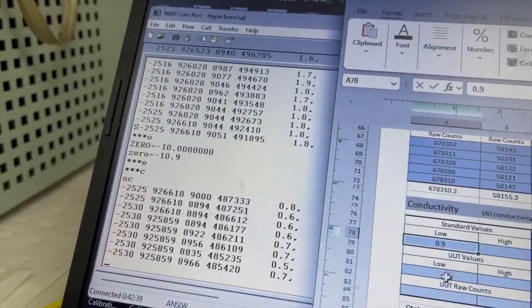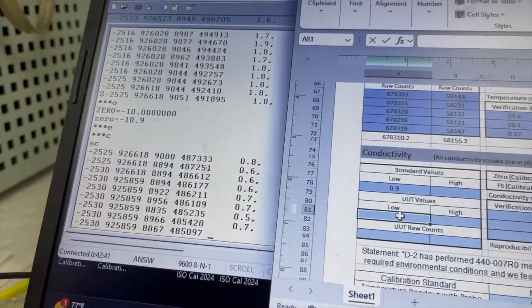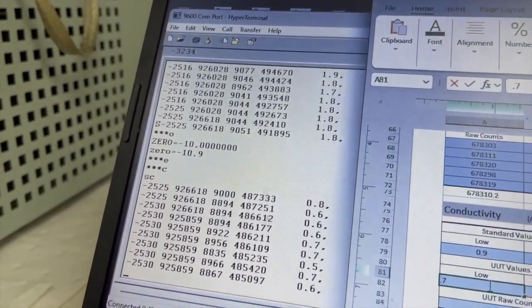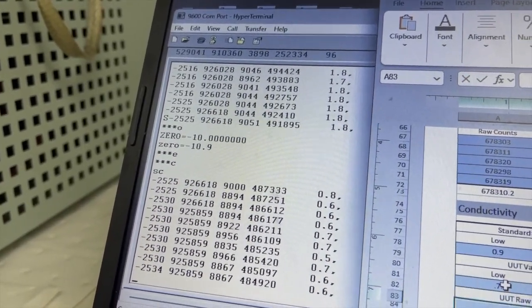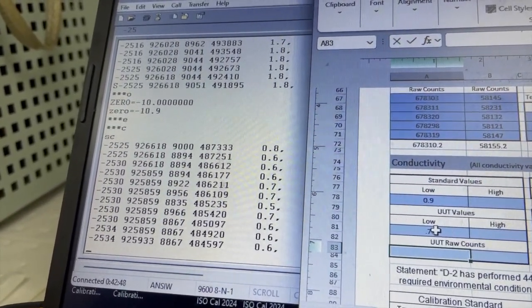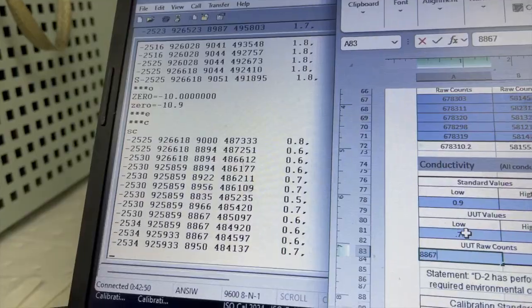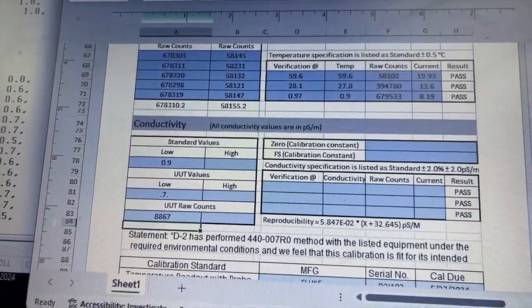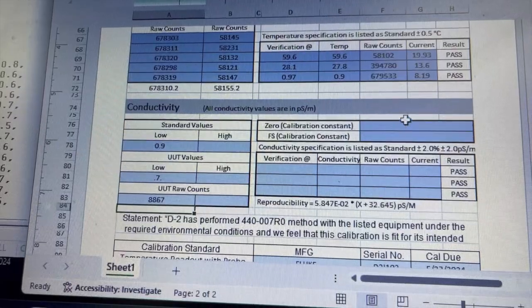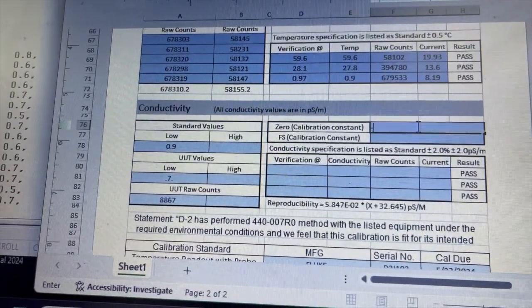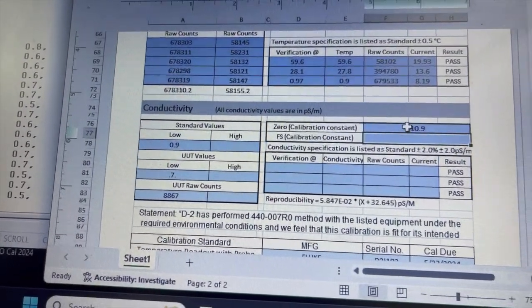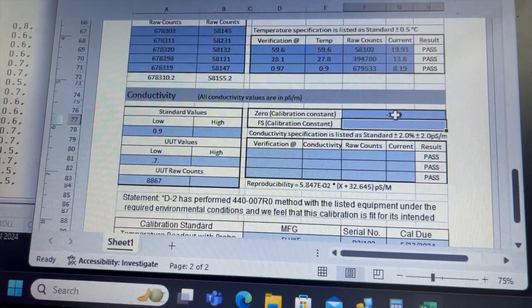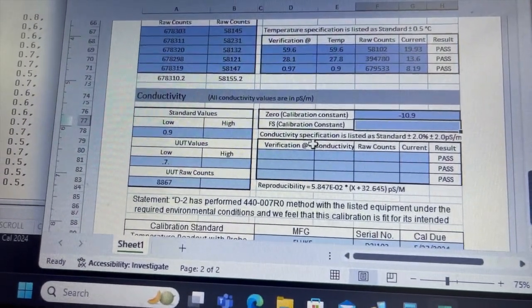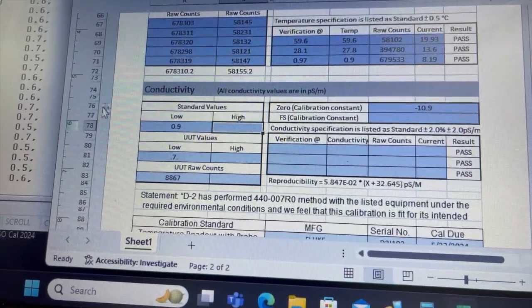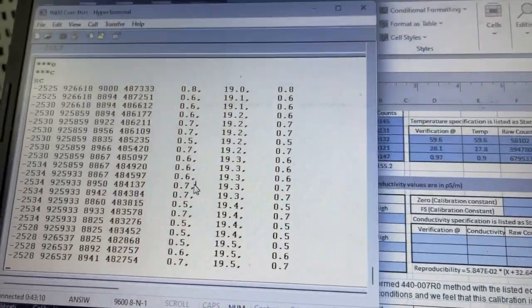So that is perfectly fine. 0.7, and we have a raw count of 8867. So we record all that down right there. We go over here and record our 0 value, say -10.9, which is a pretty standard 0 value to have. Now we need to get our full scale value.